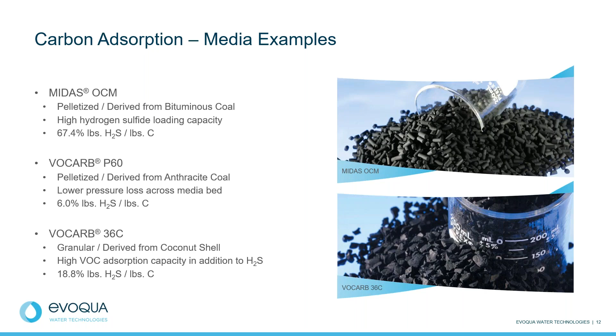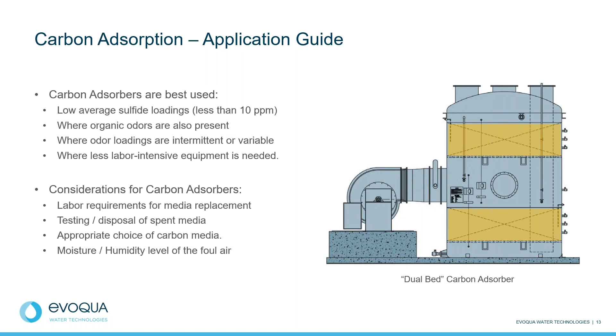And as a guideline, carbon adsorption systems are best used for average sulfide loadings less than 10 ppm and where organic odors might also be present. And just like the chemical scrubbers, these systems can also be used in applications that have variable or intermittent odors and where less labor intensive equipment might be preferred. However, we do need to keep in mind that some labor is required for regular media replacement every 1 to 2 years or so. During this process, the carbon will need to be tested for safety and disposal considerations. We also need to make sure that we're using an appropriate choice of carbon media based on the level of odors that need to be treated. And then lastly, with some types of carbon, mainly Midas OCM, the humidity of foul air can become an issue. So we do need to include a mist eliminator before the carbon vessel to keep moisture from entering the system.